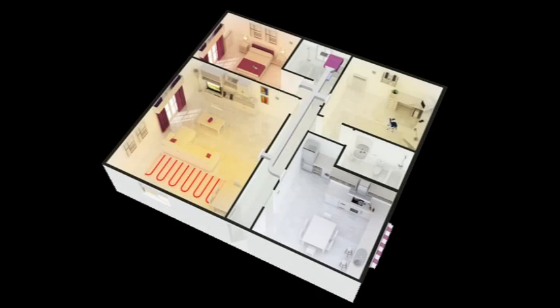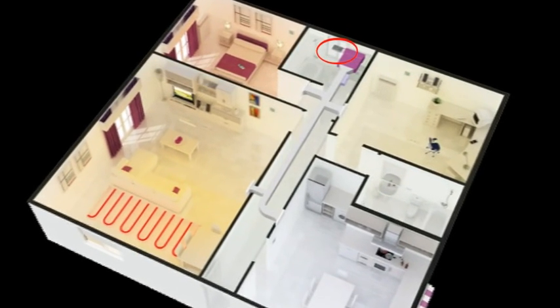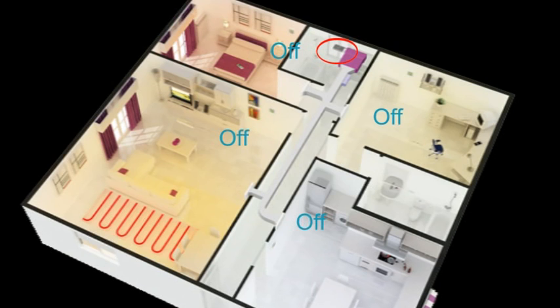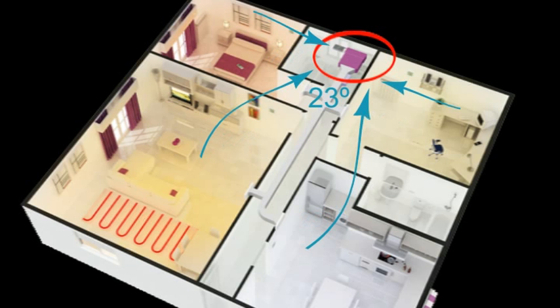The Airzone communication gateway sets the setpoint temperature in the AC unit depending on the working mode, the number of zones on demand, and each zone's setpoint temperature, looking for an increase in thermal comfort and energy savings.